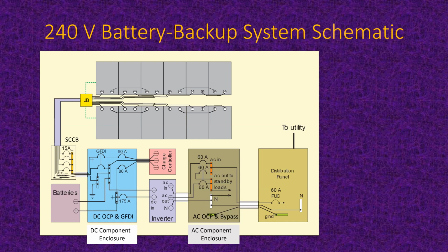So the inverter sends it out to an AC component enclosure which has a bypass switch in it. They used to do this with inverters because they weren't really sure. They wanted to make sure that you'd get power to the distribution panel, the bypass panel, even if the inverter went bad. So they had a mechanism with an interlocking switch so you could bypass that inverter for maintenance purposes. Again, an obsolete piece of equipment. You rarely see these anymore, but that's the history on it.